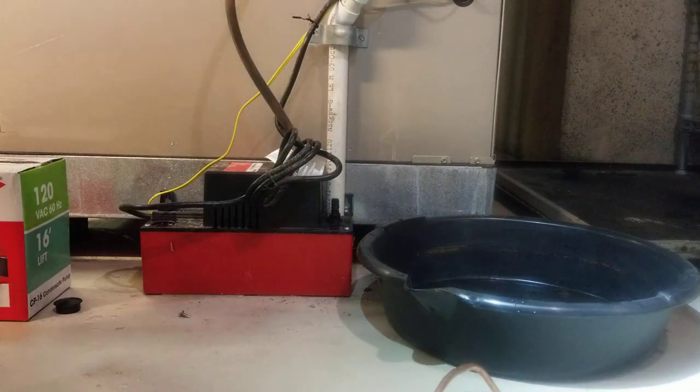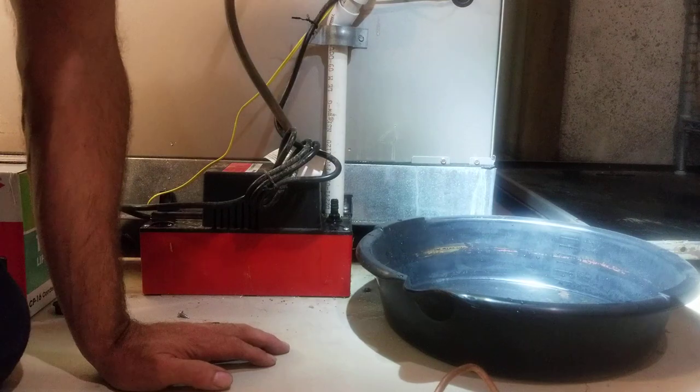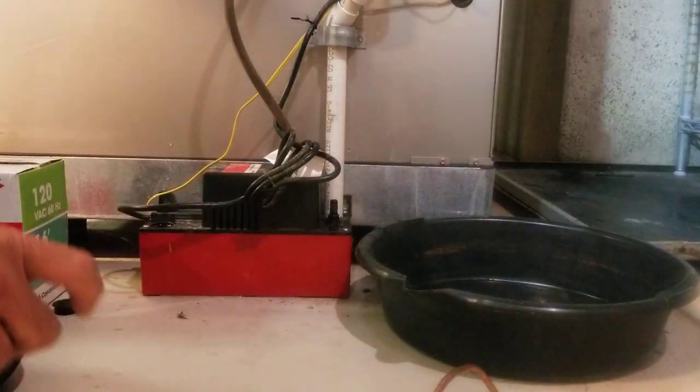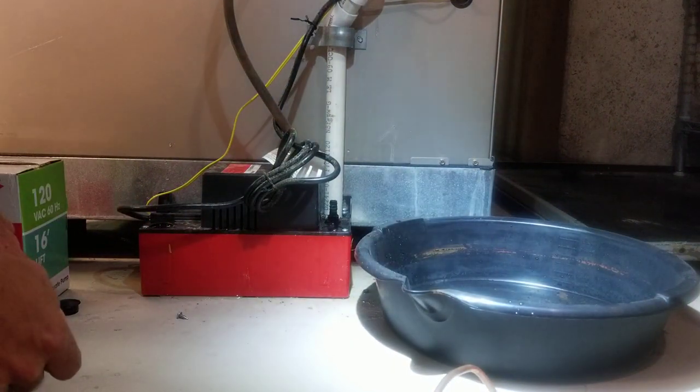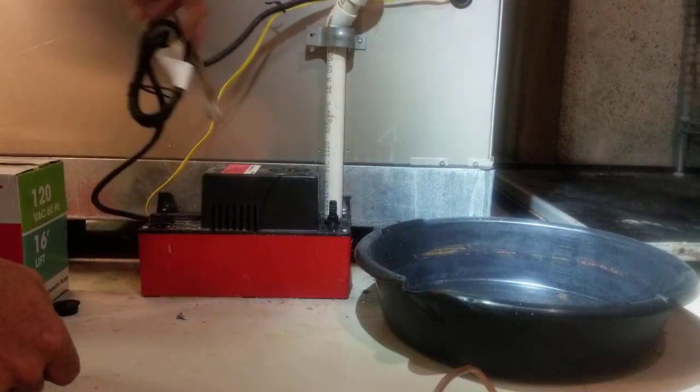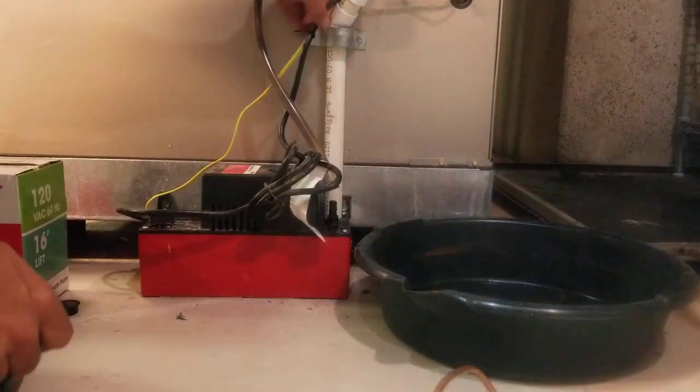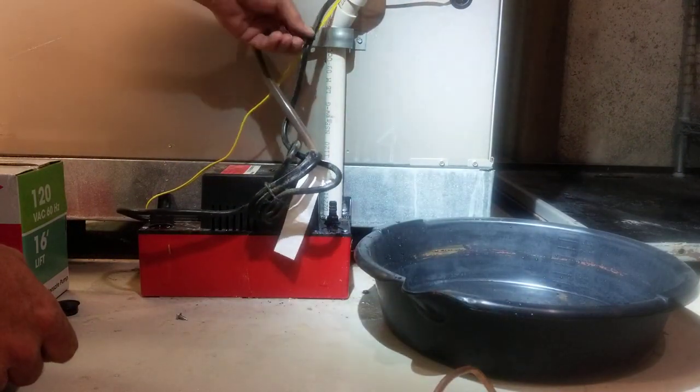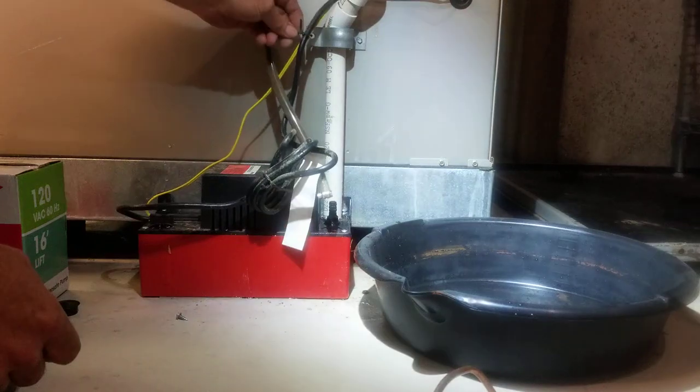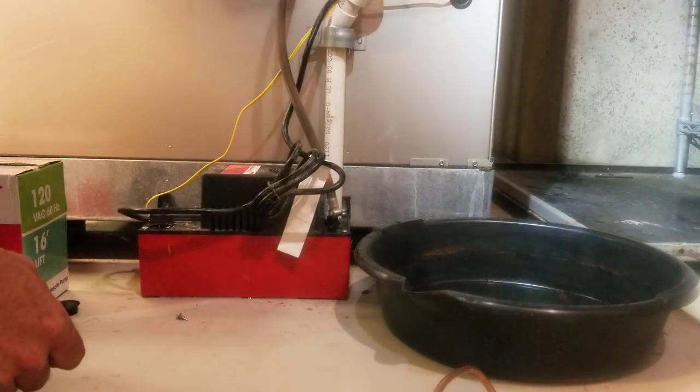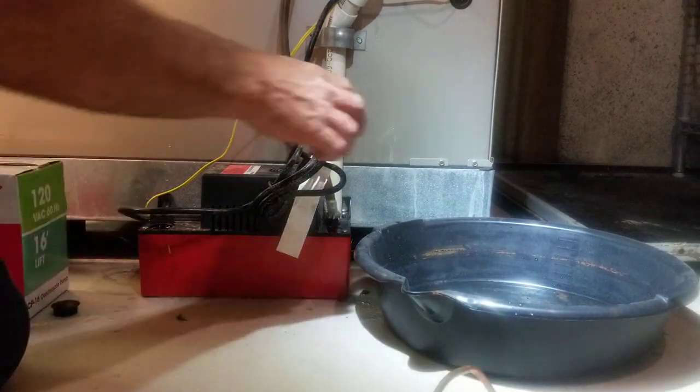Okay, got a call today for water on the floor and condensate drain is plugged. But as soon as I cleared the drain, pump filled up and it's not pumping, so let me plug it in.